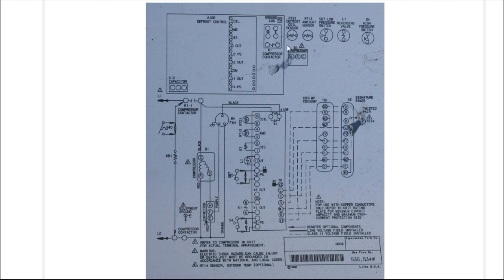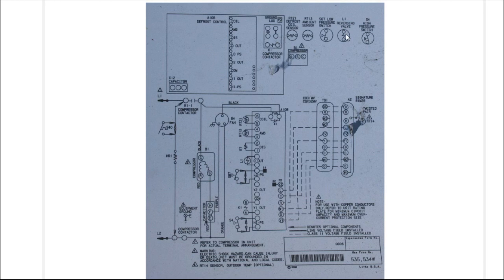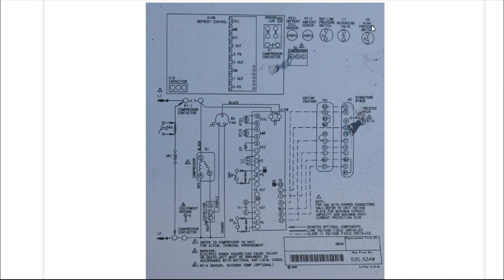Here at the top it shows your different components. For example, S4 is a high-pressure switch and it shows you what it looks like. L1 is the reversing valve and shows you what it looks like, and so on. When you look down in the ladder diagram and you see S4 and you're not quite certain what that is, you can go back up to your legend and see that S4 is the high-pressure switch. The Lennox one does happen to have H I dash P S, which stands for high-pressure switch.